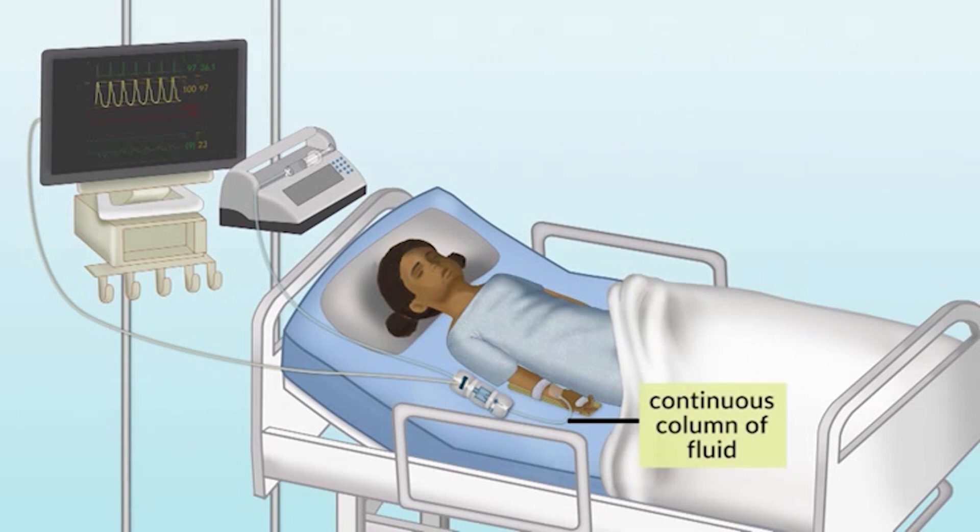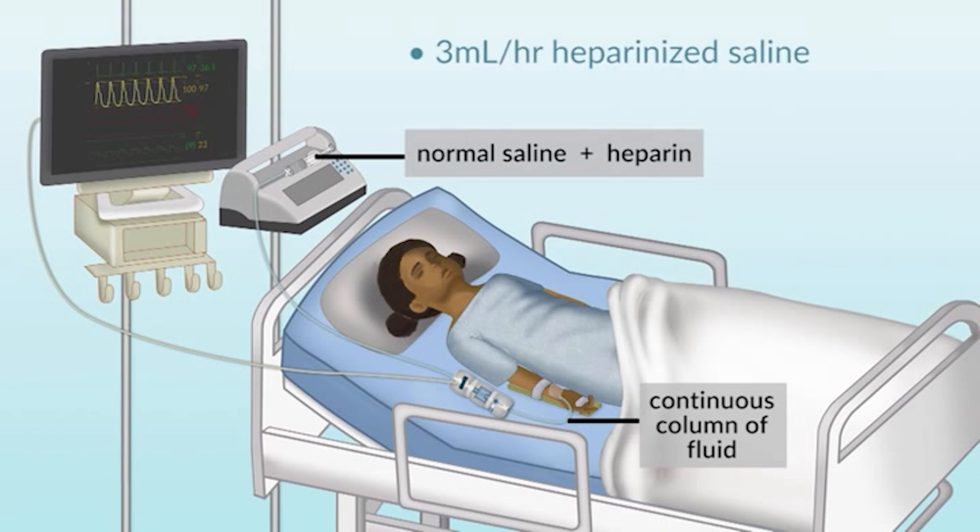We have this continuous column of fluid, and the transducer is generally hooked to a flush system — in this case, normal saline with a little bit of heparin added, running at about 3 mLs an hour, which is pretty typical and may vary from institution to institution. That's a volume of fluid necessary to keep the system free of clot and to prevent any thrombus forming on the ends of the catheters, which would degrade the quality of the system and obviously creates a potential risk to the patient.